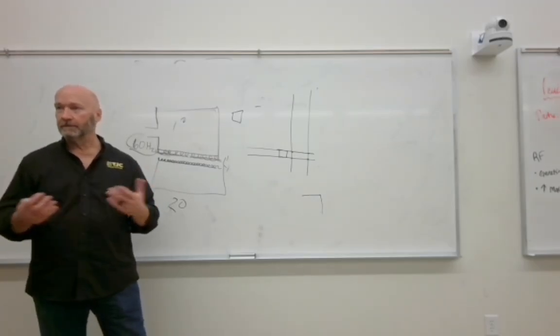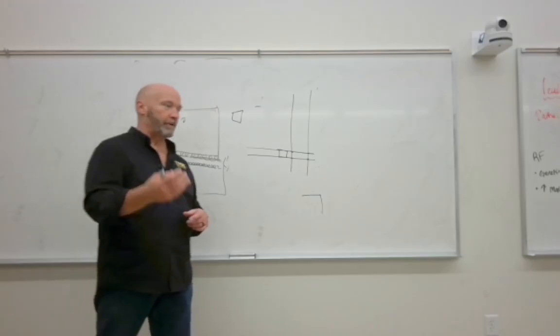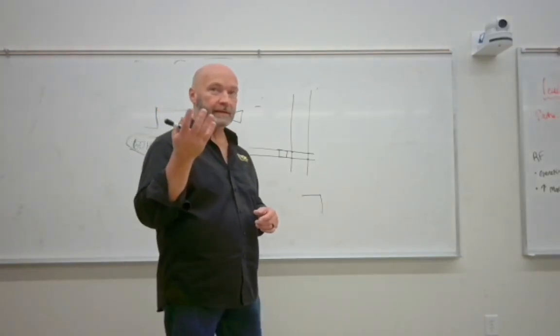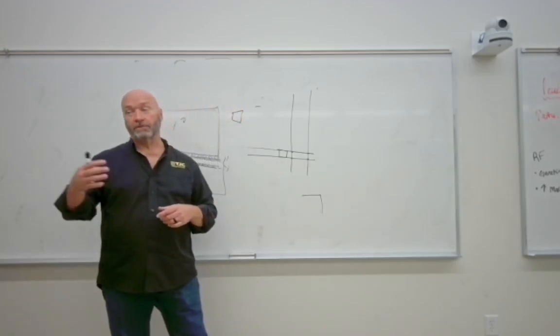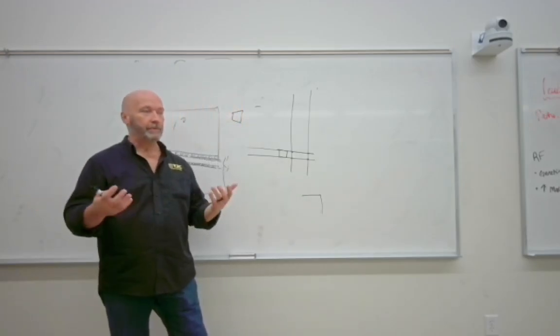So energy level is one way. Fluoroscopy units use high kVp, naturally high kVp, to reduce patient dose, and also save heat on the X-ray tube, but reduce patient dose.